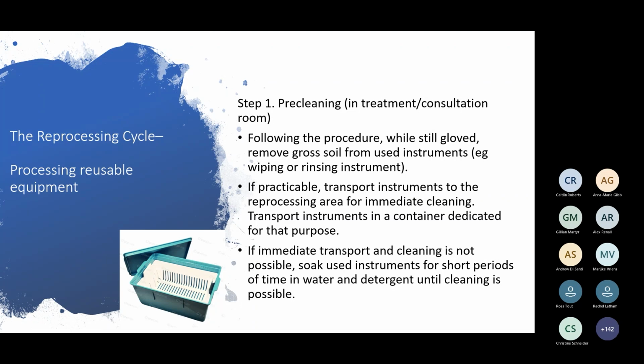If immediate transport and cleaning is not possible, so this could be like for some podiatrists who do home visits, that sort of thing, then you can soak your used instruments for short periods of time in water and detergent until cleaning is possible. I'm having a mental blank. There's a Clini Soak, I think it is. It's a product that's in a squeeze bottle. You can spray your instruments. It has a holding time of about 7 hours. So if you're, say, a mobile podiatrist or something like that, you can use products like that to spray your instruments, put them back in the sealed container until you can get back to actually reprocess them properly.